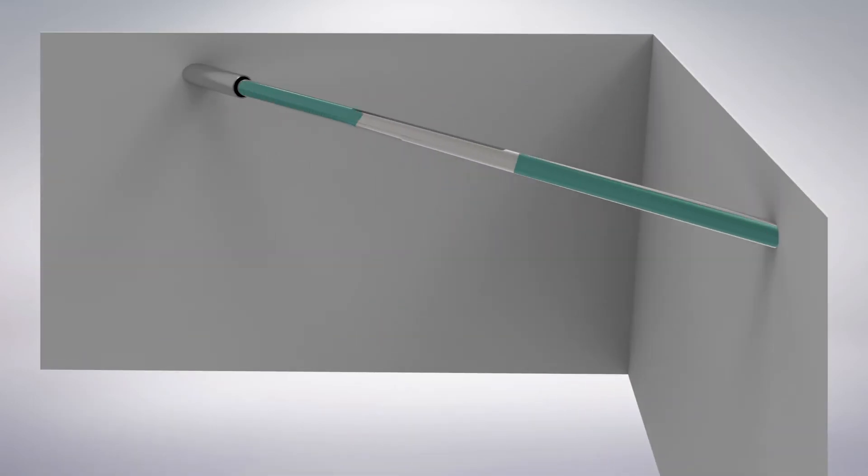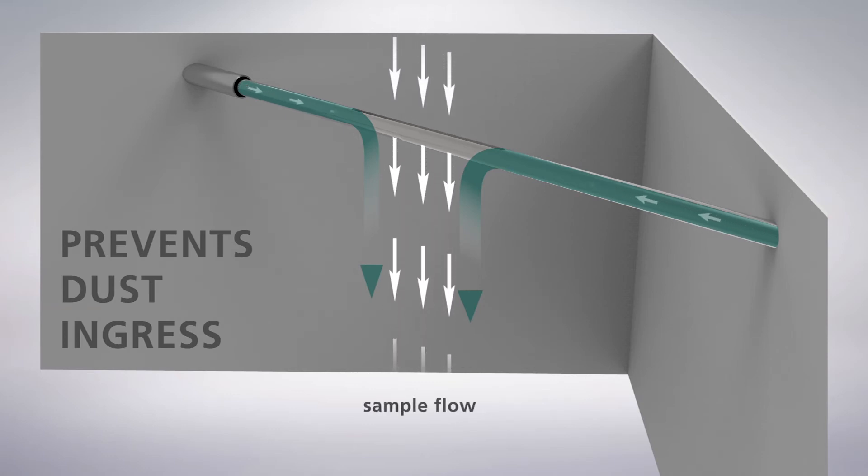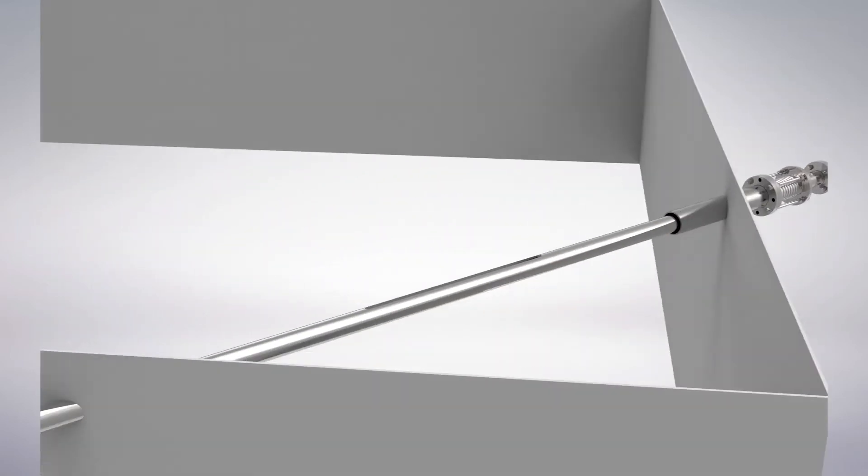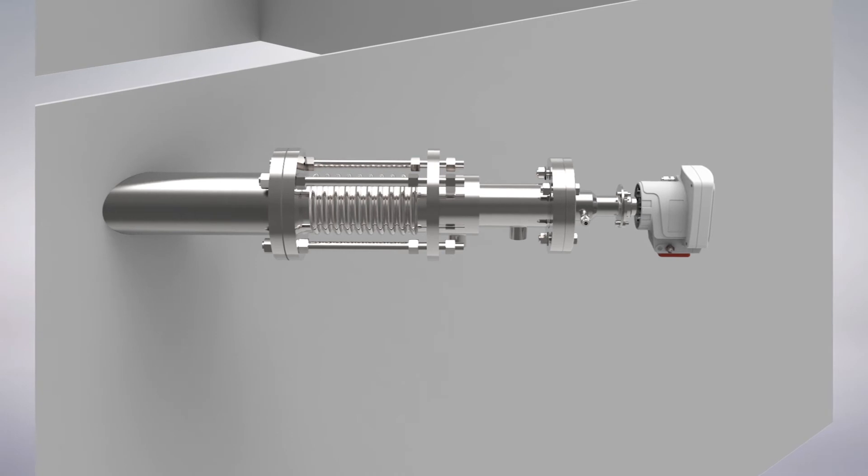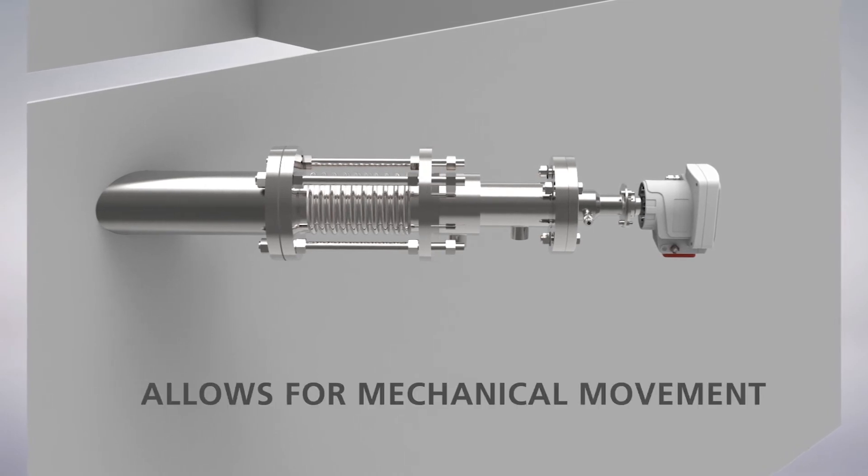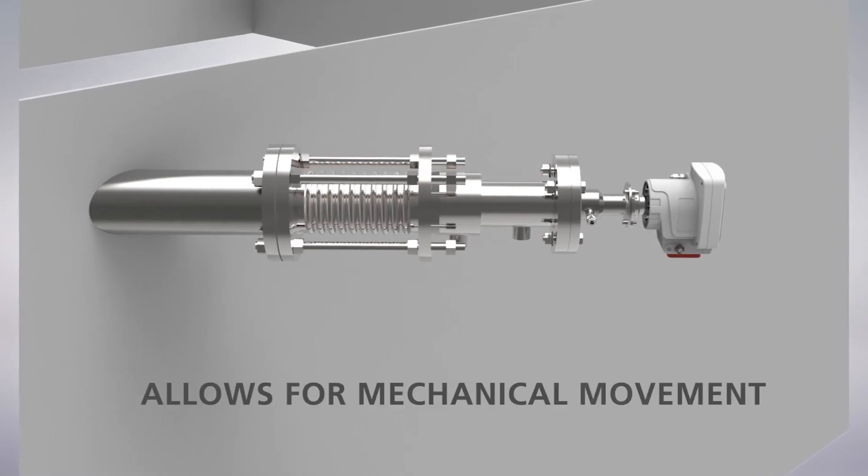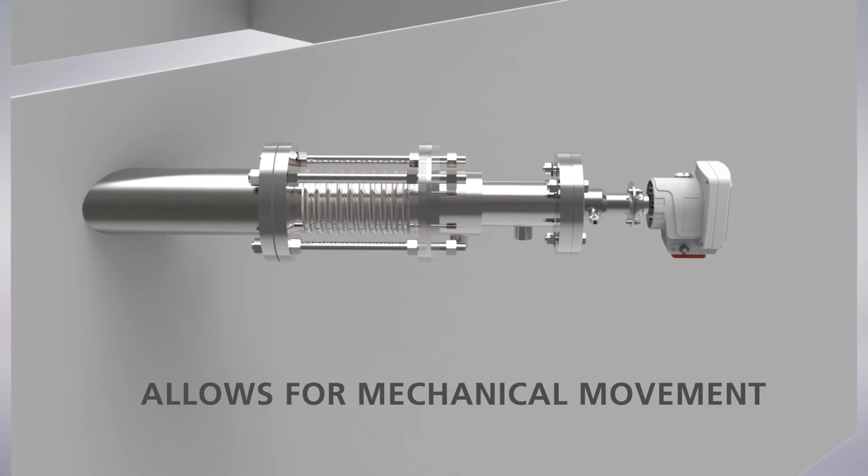This performance is enhanced by the installation of Servomex's fixed pipe solution. It minimizes contact with the sample stream by deflecting dust around the fixed pipe, protecting the laser beam. In addition, the Laser 3 Plus solution has a unique way to resolve mechanical movement, allowing for process movement and thermal expansion while keeping maximum beam alignment.